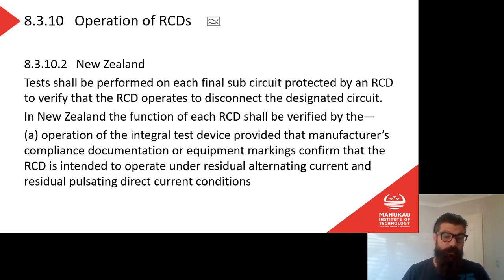Again, we're going to use a special meter, an RCD tester, and we connect the RCD tester to the RCD, and we push the button, and the RCD tester will trip the RCD, and it will measure how much current it took and how fast it tripped. At a very basic level, we don't need to know any of that information at all. All we need to do is plug it in, push the button, and decide whether that is a pass or a fail. Further on in the course, we'll get into great detail about how an RCD operates and what's actually happening when we run that test.